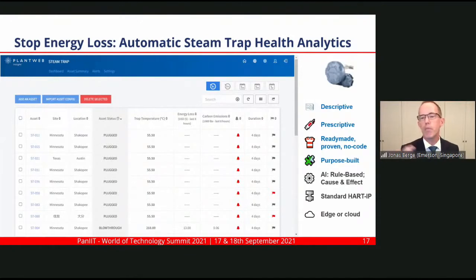So what plants are doing is putting in sensors like the one you see on top right. It sends acoustic noise and temperature data to the analytics that then tells you the health of the steam trap, and whether it's failed by blowing steam or trapping condensate. So it's descriptive analytics, not just telling you it failed or there's an anomaly. Now you know you need to replace the steam trap - that's prescriptive analytics. And all of this analytics is ready-made, tested and proven in many other sites.